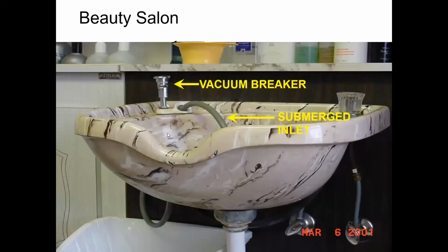At beauty salons, you'll see they have all these sinks. They're rinsing hair, dyeing, shampooing, whatever they're doing. We've got various chemicals that could be applied. And in this case, we also have this hose that's been left down into the sink as a submerged inlet. If we follow that hose going back down, you can see there's a little U-shape, a little loop down below the sink, and it's protected by a vacuum breaker. But that's something you want to check to make sure that protection is in place. If that wasn't there, the submerged inlet would not be acceptable. That would be a cross-connection risk.